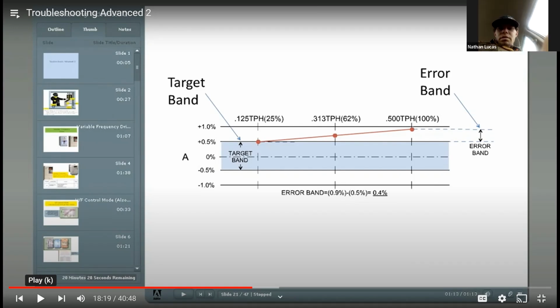Because if you're calibrating your scale at 100 pounds and you're 2% off at 100 pounds, that 2% is going to stay there when you're at 1,000 pounds. So the bigger the number, the bigger your percent off is going to be. If you're 100 pounds off at the lower weight, you might be 600 pounds off at the higher weight. So the higher you can get that number, the more clarity you'll have as well.